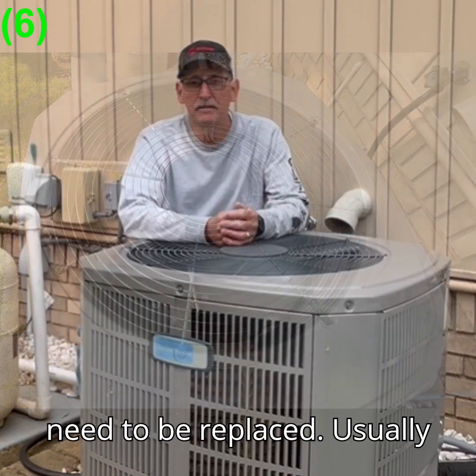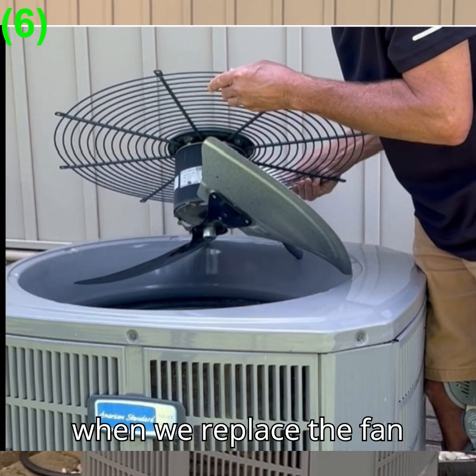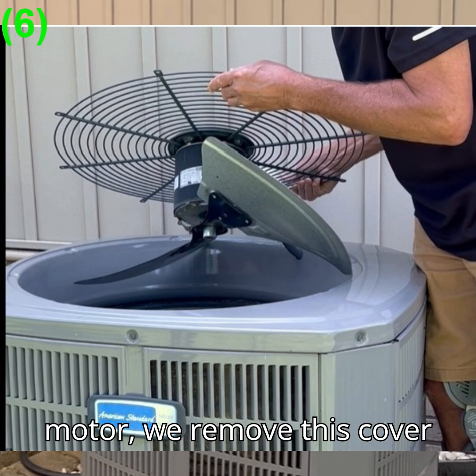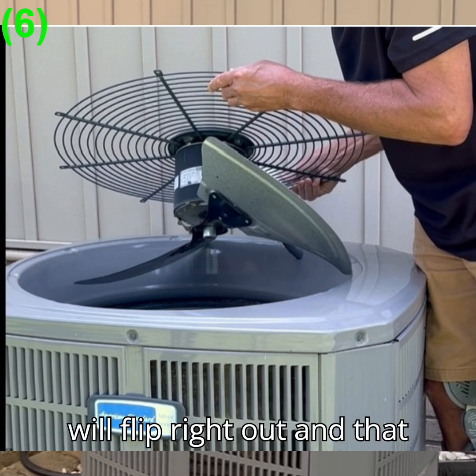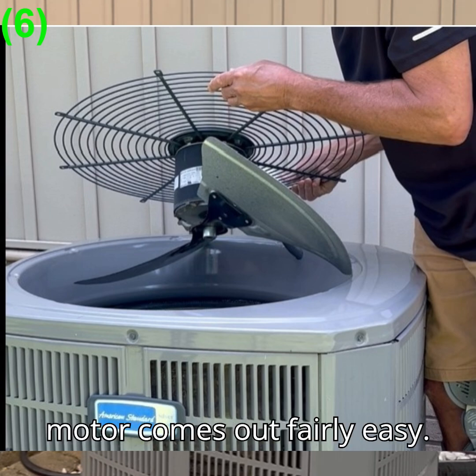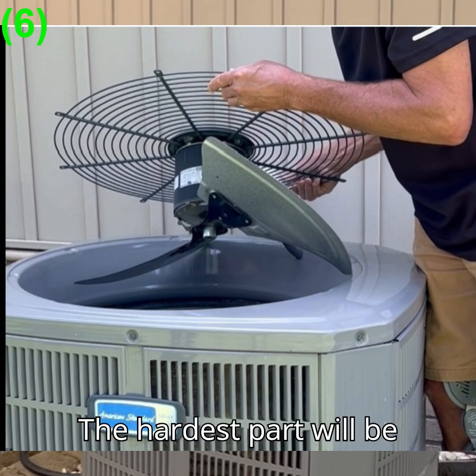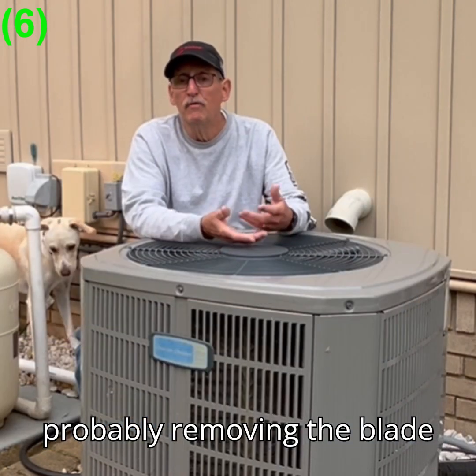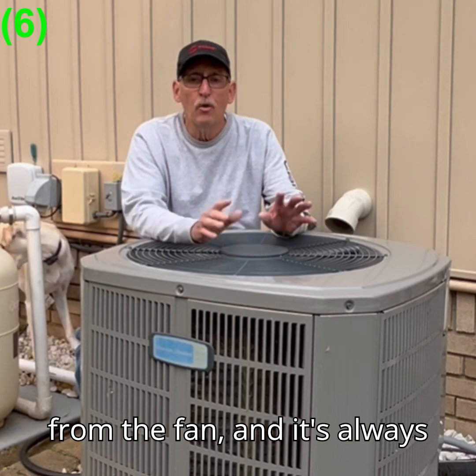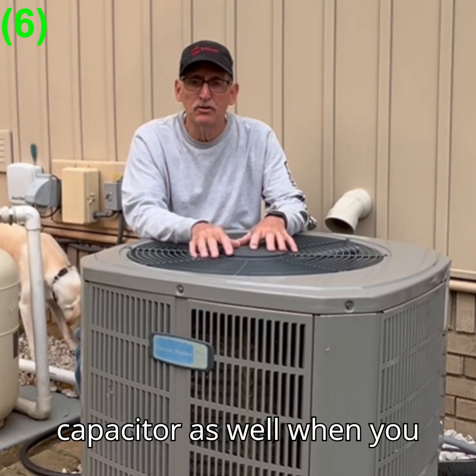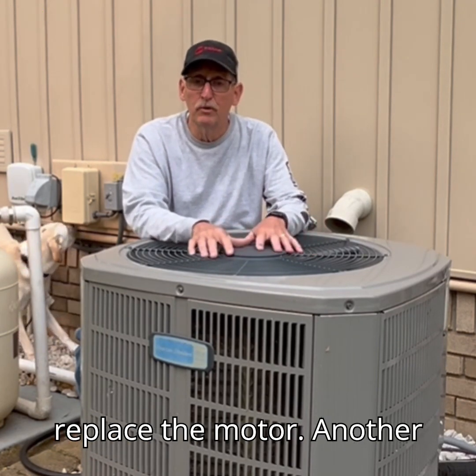But generally, that means the motor has some kind of problem, like the motor is just dying and will need to be replaced. Usually, when we replace the fan motor, we remove this cover here, these screws, and this will flip right out. And that motor comes out fairly easy. The hardest part will be probably removing the blade from the fan. And it's always a good idea to replace the capacitor as well when you replace the motor.